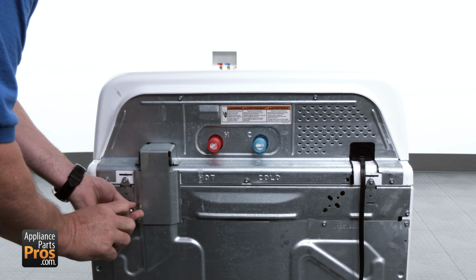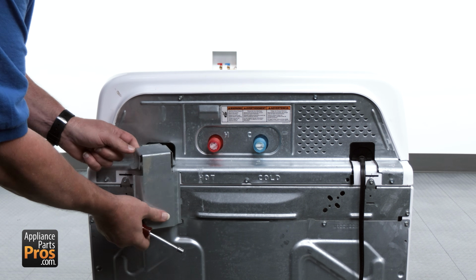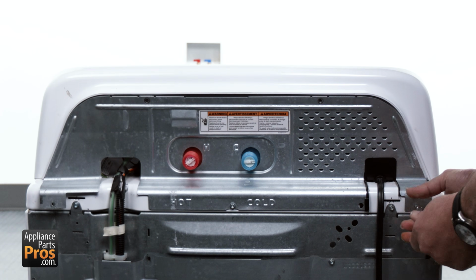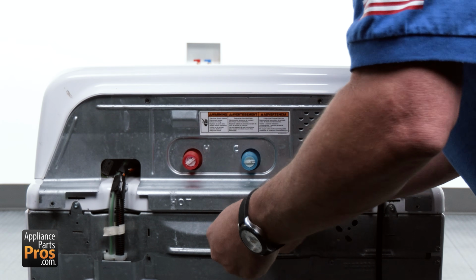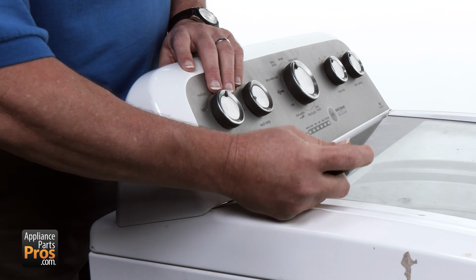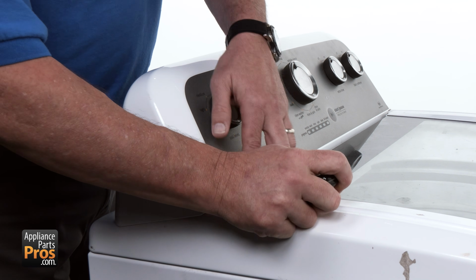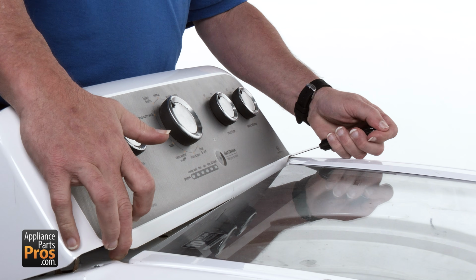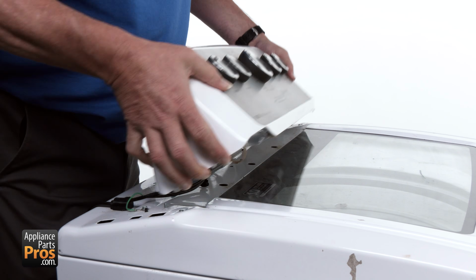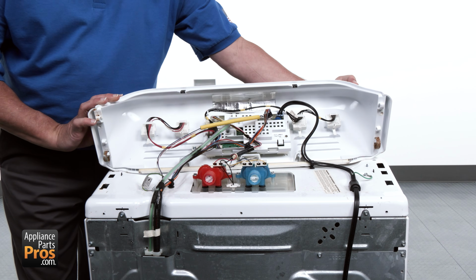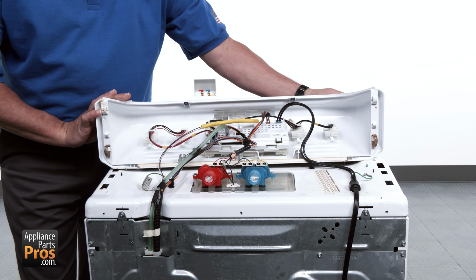To access the control board, begin by using your 1/4-inch nut driver to remove the screws securing the back panel of the control console. Once the screws are removed, slide a putty knife under the corners of the control panel and release the spring clips. Then lift the console up and back. This will expose the main control board and its wiring connections.